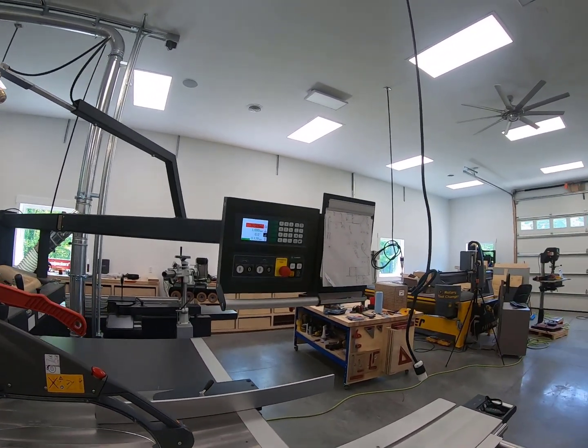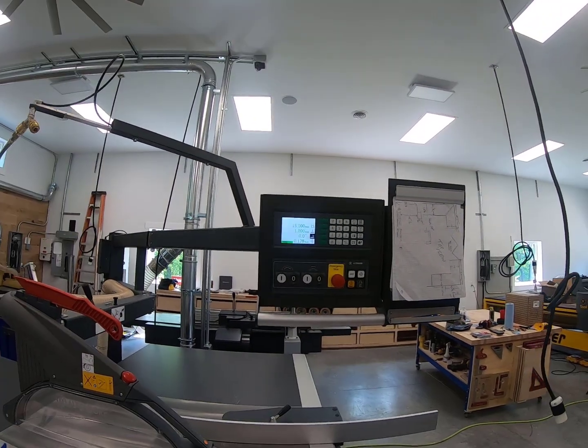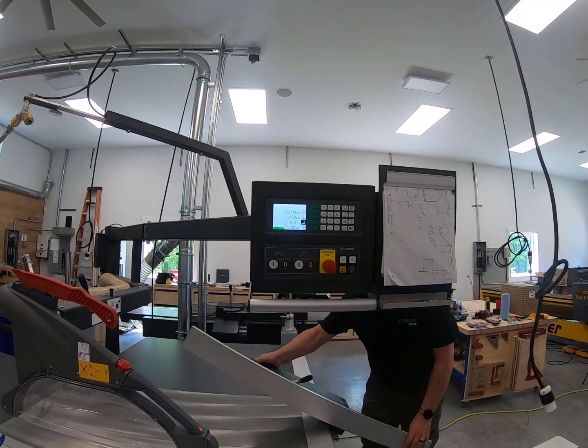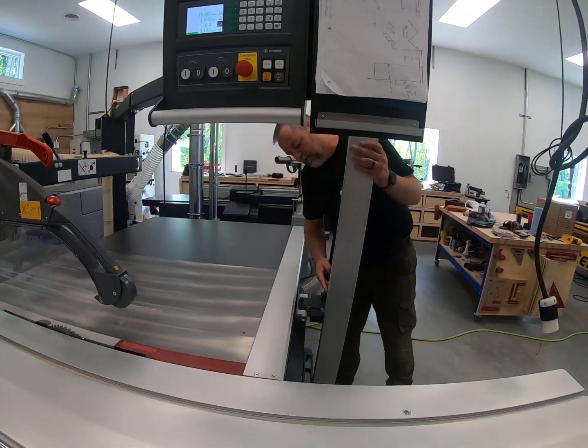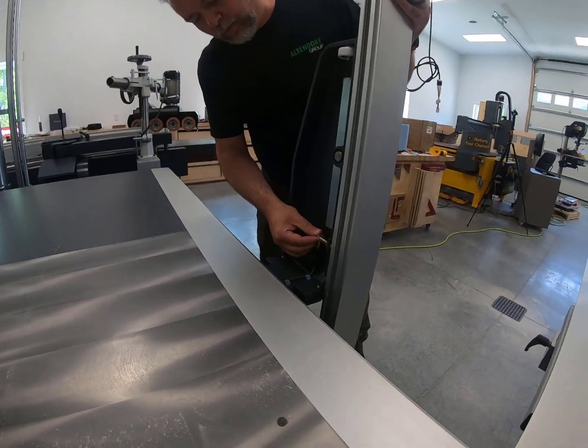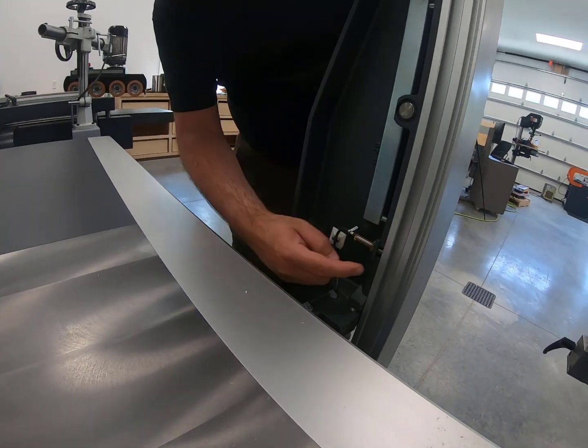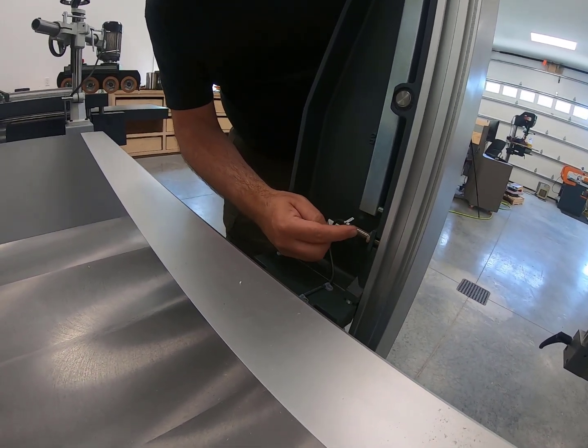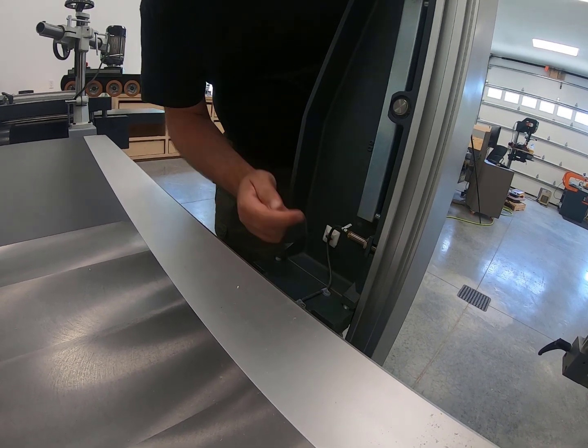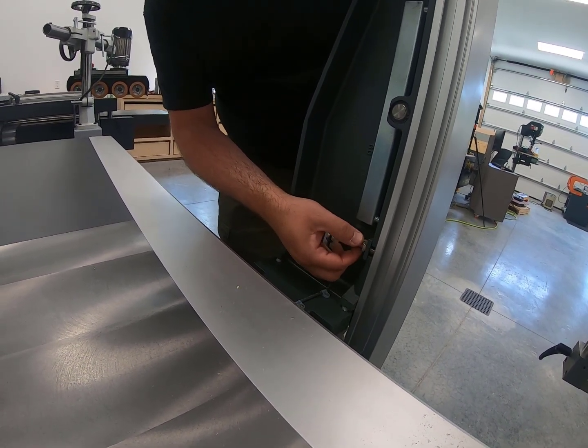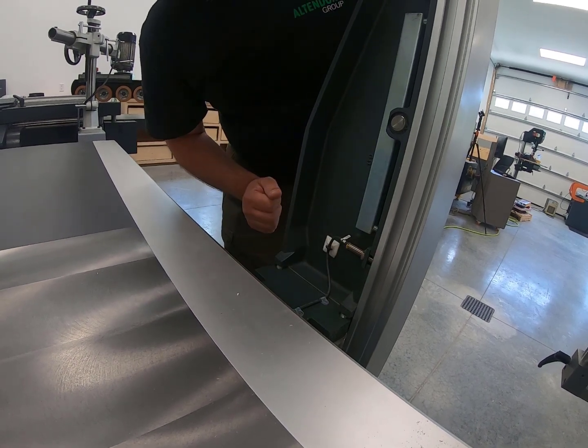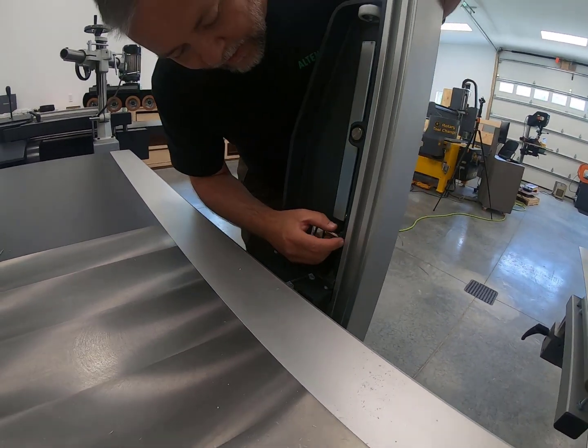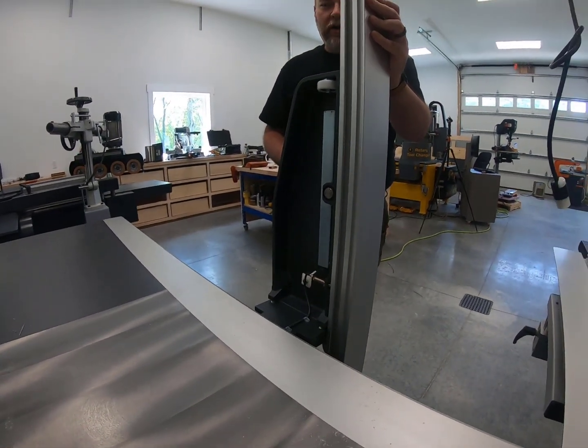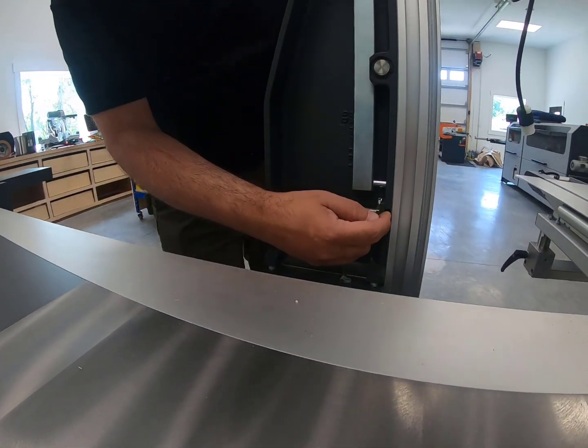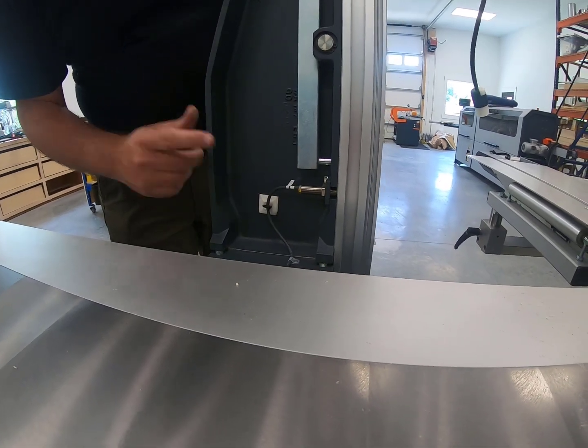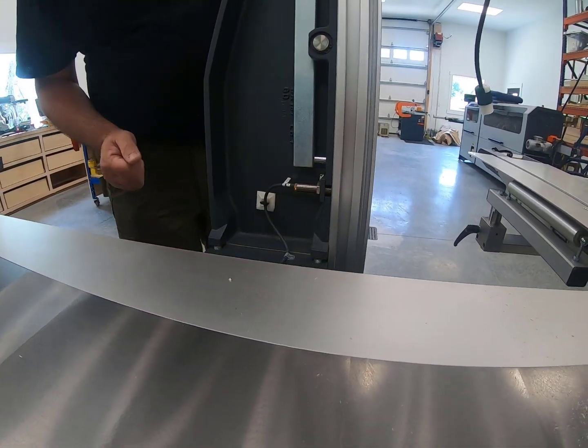Press start. So while you shake it, you always lift this up and check if this light is on. Sometimes you can wiggle it if you notice it coming on and off. If it's in this position and it's off, that means the sensor adjustment is off. You loosen up this nut here and you can go in and out to adjust it. I think as of right now there's about a 0.01 or 0.02 millimeter spacing, so you can always take a feeler gauge and check it.